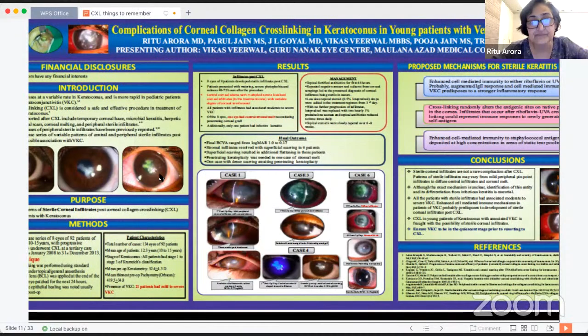Corneal thickness. So preoperatively, as I said, corneal thickness ideally should be around 450 microns. And before we start the UV ray, and the patient is exposed to UV rays, it should be at least 390 micron plus. So now it has become mandatory in our setup that we do intra-op pachymetry and only then continue with the cross-linking. At times, the thickness is a problem because when we do it on Pentacam and on OPD-Scan, sometimes we do not get readings which match, or they may be, say, 370, 380 micron, you do not know.